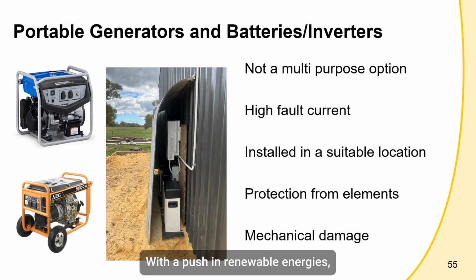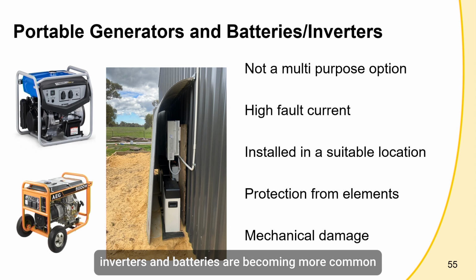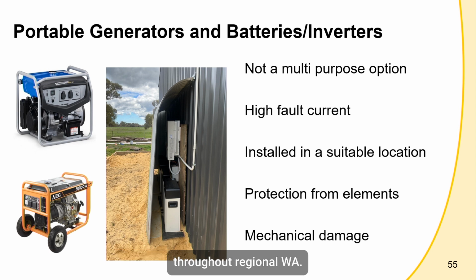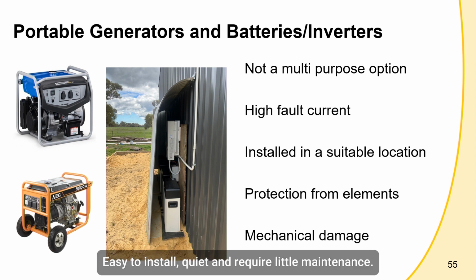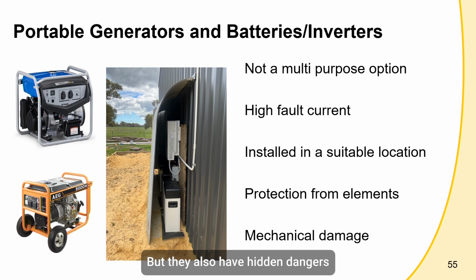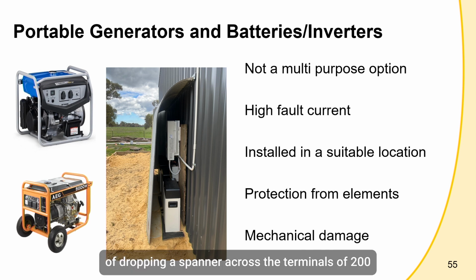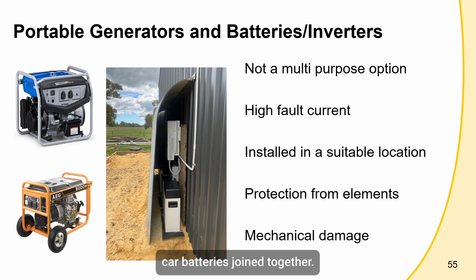With the push in renewable energies, inverters and batteries are becoming more common throughout regional WA. They're easy to install, quiet, and require little maintenance. But they also have hidden dangers. Lower voltages and much higher currents. The available fault current in a regular battery energy storage system can exceed 20,000 amps. And that's the equivalent of dropping a spanner across the terminals of 200 car batteries joined together.